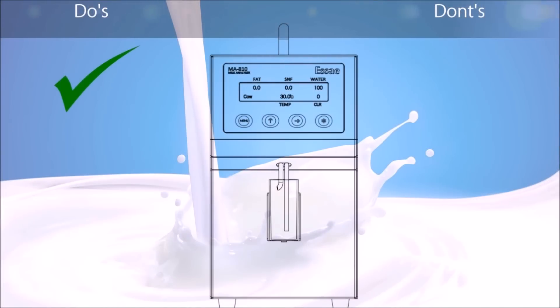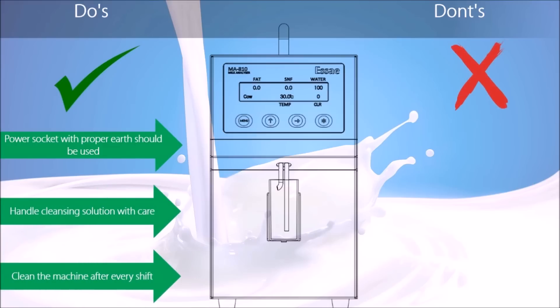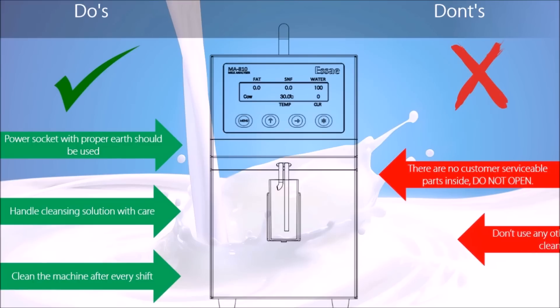Coming to the do's and don'ts of handling the machine. Please use power socket with proper earthing. Cleansing solution should be handled carefully. Machine should be cleaned after every shift. The machine should not be opened. There are no customer serviceable parts inside. No other solution should be used to clean apart from the one provided with machine.